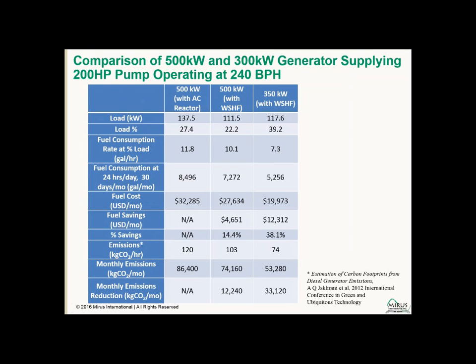So finally, let's look at the actual field measurements and calculations that we did to determine the fuel savings that resulted from the harmonic mitigation. So with a 500 kilowatt generator with a VFD just equipped with an AC line reactor, as we found the situation, it was 137.5 kilowatts. When we added our filter, it dropped to 111 kilowatts.